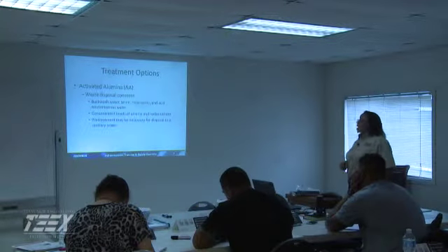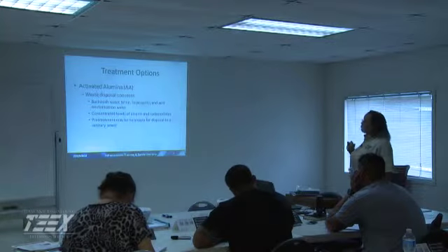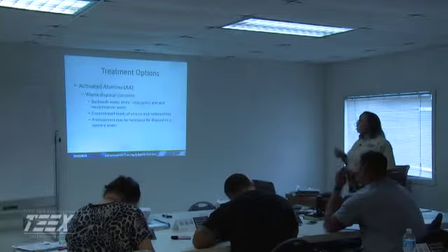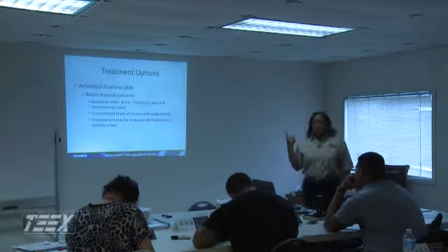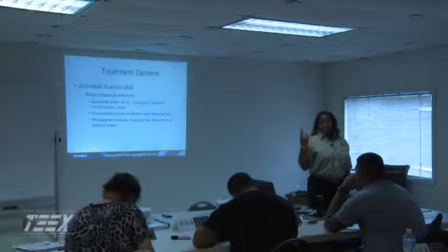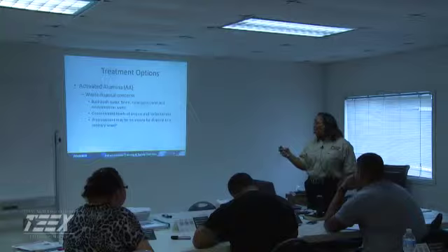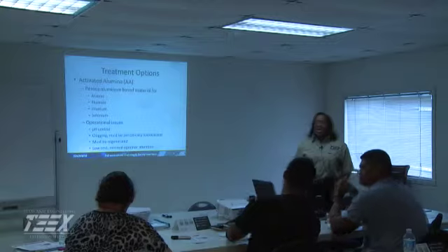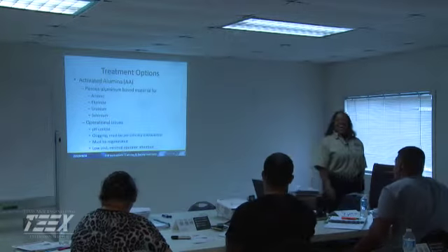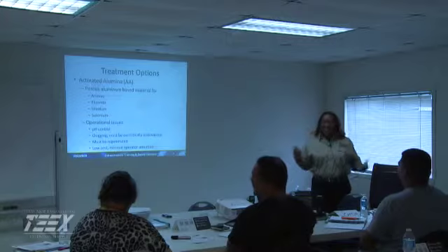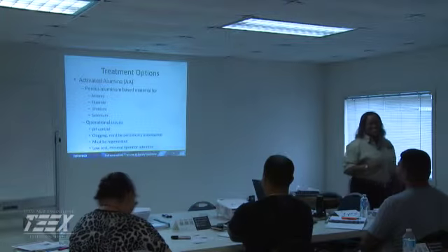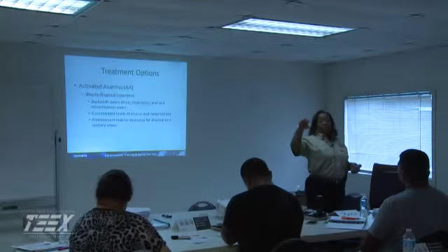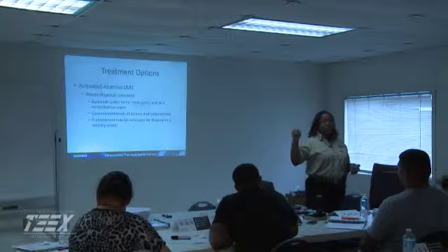Other concerns with your activated alumina is your wastewater or waste product, so to speak. You're going to have backwash water to deal with. What are you going to do with it? Put it in the sewer. I can't just put it in the sewer now, I have all this concentrated stuff of arsenic, fluoride, uranium, and selenium in the backwash.